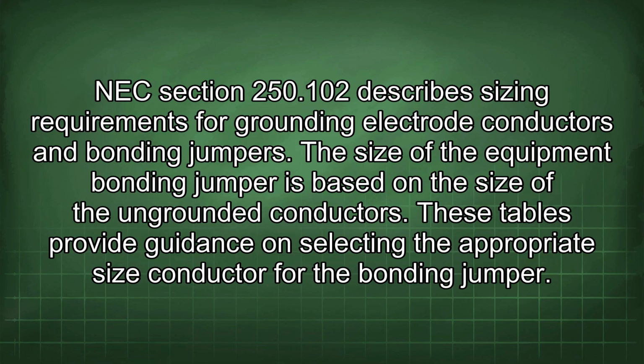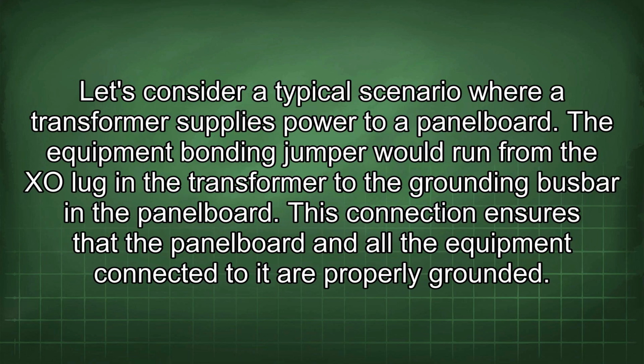NEC Section 250.102 describes sizing requirements for grounding electrode conductors and bonding jumpers. The size of the equipment bonding jumper is based on the size of the ungrounded conductors. These tables provide guidance on selecting the appropriate size conductor for the bonding jumper. Let's consider a typical scenario where a transformer supplies power to a panel board. The equipment bonding jumper would run from the XO lug in the transformer to the grounding busbar in the panel board. This connection ensures that the panel board and all the equipment connected to it are properly grounded.